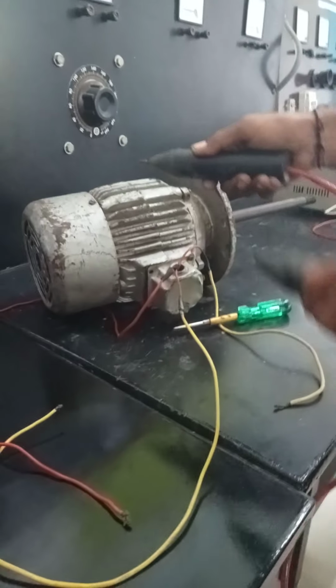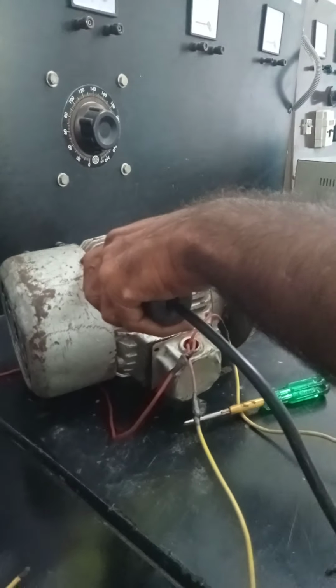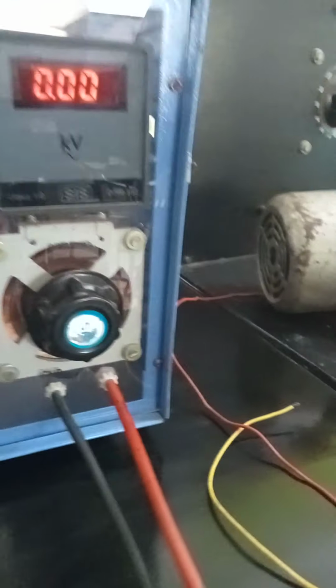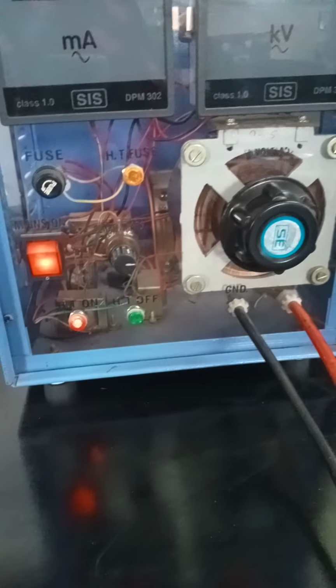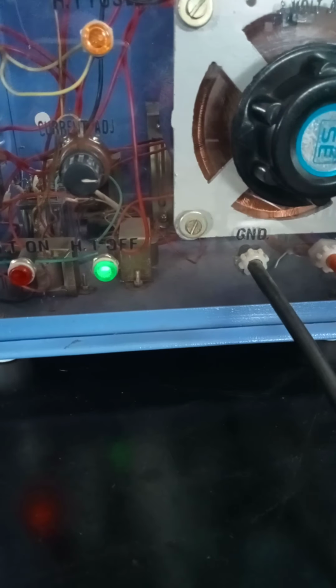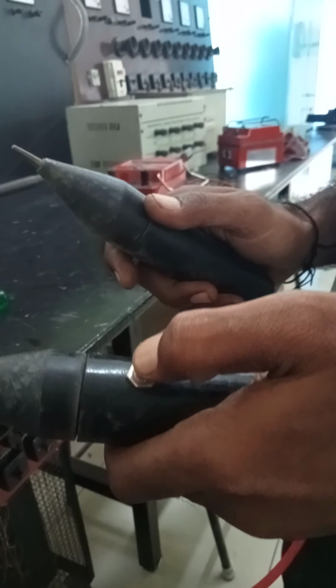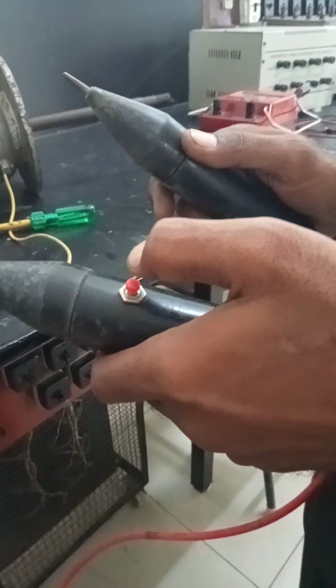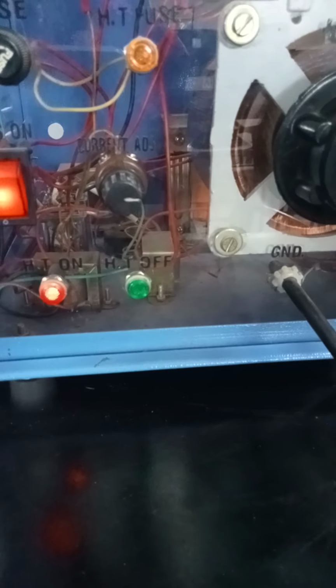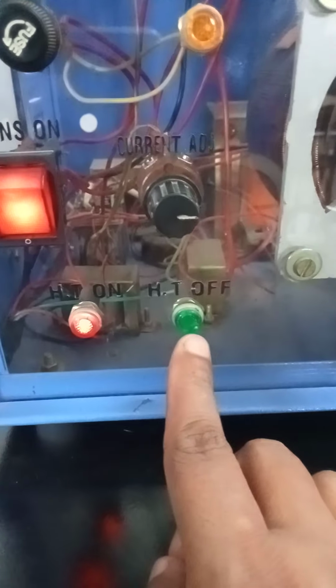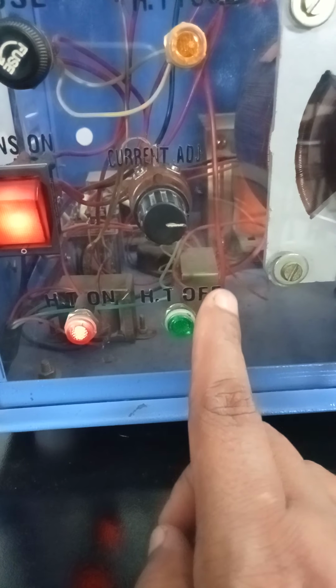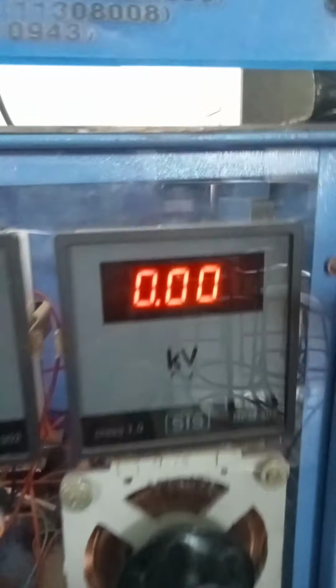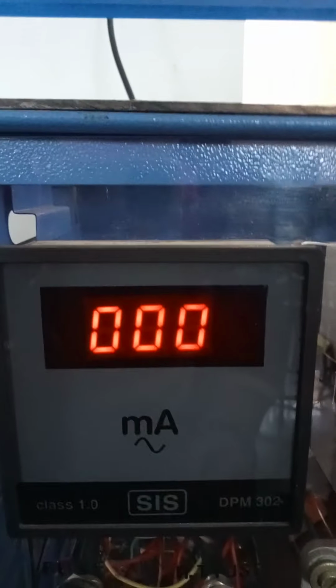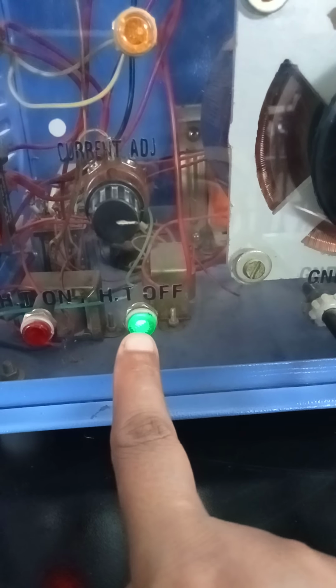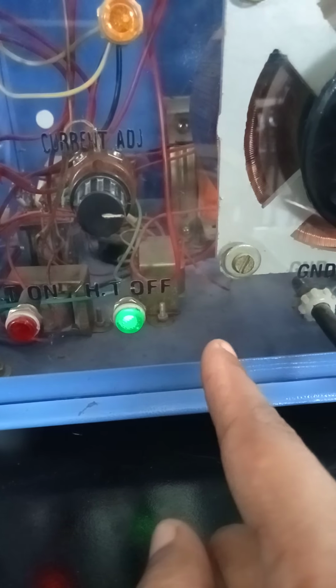Now if we short circuit both the terminals, if I check, see, through the body it is short circuited. Now you can hear the buzzer sound coming. See, HT is off. Now again we will reset this switch and it is on. So in order to stop this buzzer sound, we have to press this control switch that is provided on the electrode. So the moment the fault comes, the on is converted into off. This green light will glow and the buzzer will start blowing. So this indicates, yes, see, this indicates the moment fault comes, voltage becomes 0, current becomes 0. Why? Because the high tension supply is switched off automatically for the protection purpose.